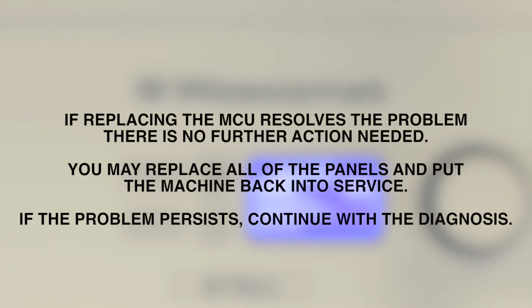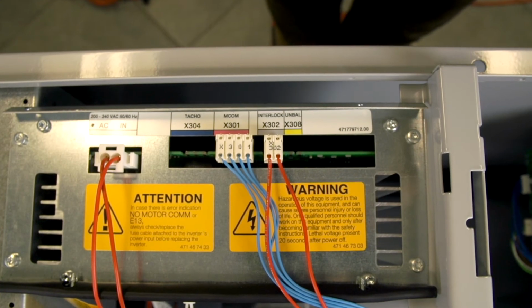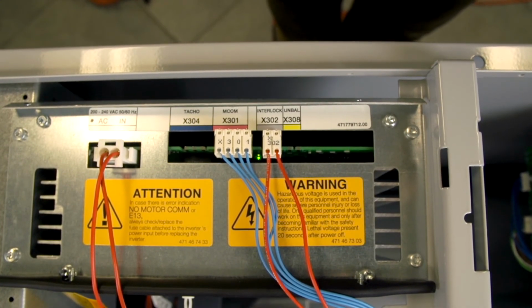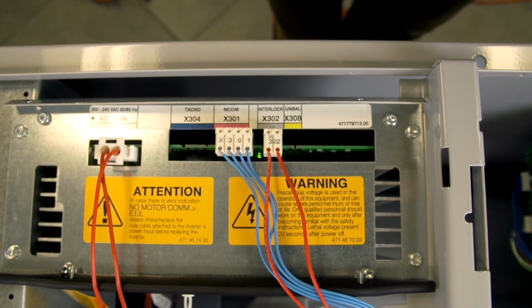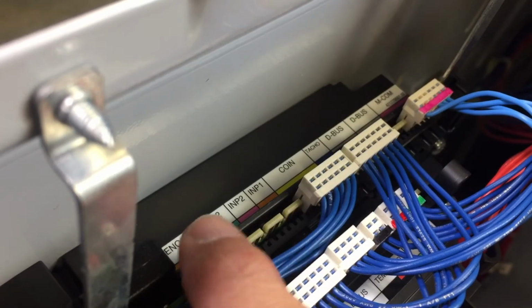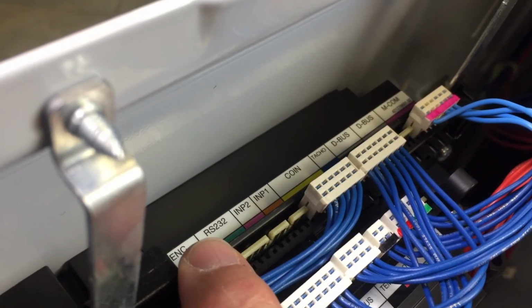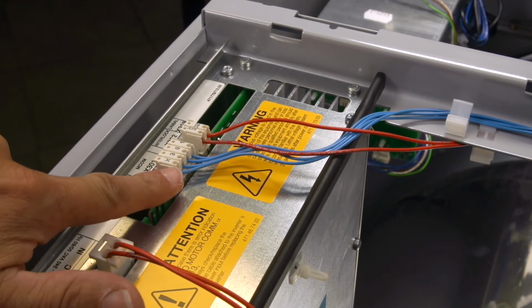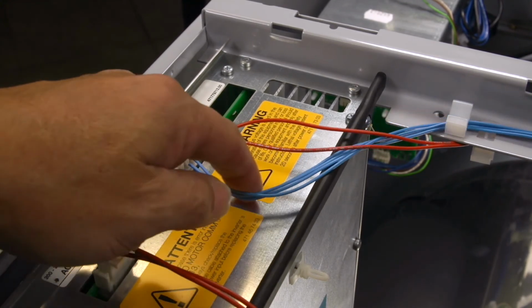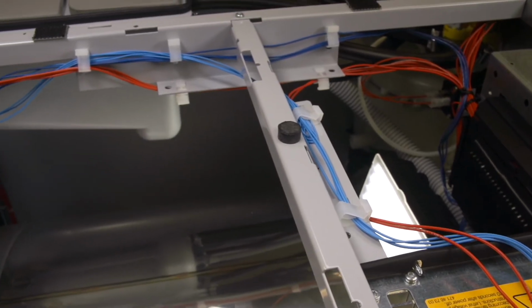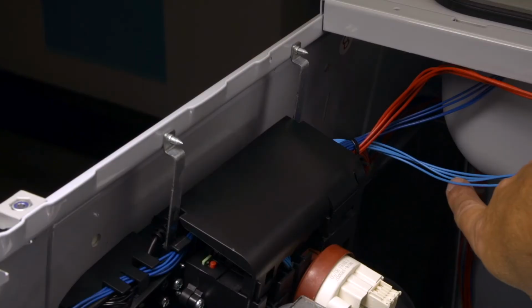If this resolves the problem, there's no further action needed. You may replace all of the panels and put the machine back into service. With the LED on the MCU blinking as described, and if the problem still exists, then it is a probable fault in the CPU PCB communication circuits or in the communication cable between the MCU and the CPU.